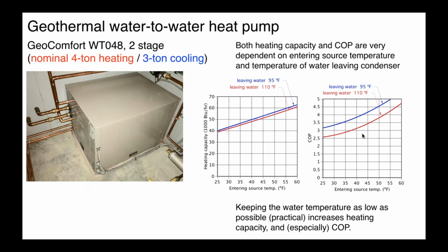It is definitely a difference from a boiler. With a boiler, you can push up the aquastat and cover up situations where the heat emitters were, let's say, lacking enough heat transfer plates or the spacing is too wide. You can compensate for that in water temperature with a boiler. And yeah, you do lose some performance, but with a heat pump, it's really important to focus around that low water temperature. And you'll see this is also the case with an air to water heat pump as well.